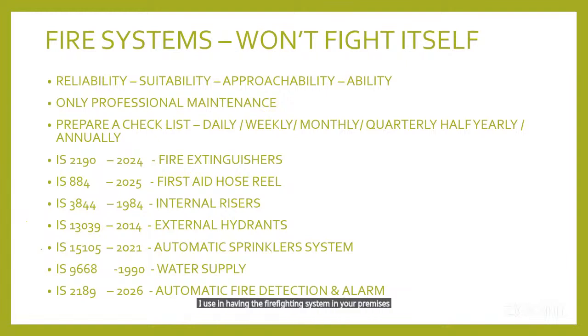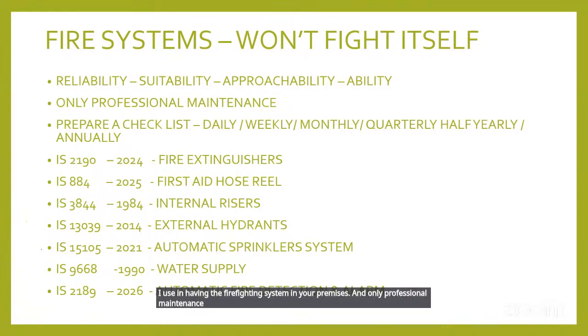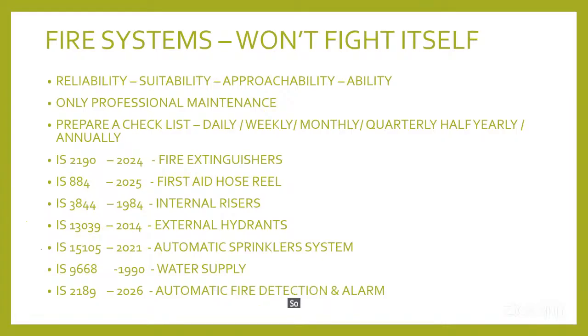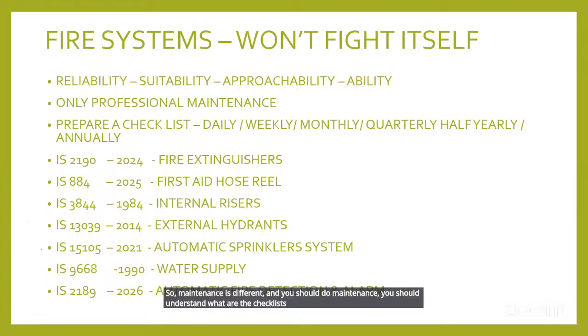And only professional maintenance counts. It is not a mere pasting of stickers on the extinguishers. I have seen many places while doing audits; only stickering is not maintenance. Maintenance is different, and you should do it. You should understand what the checklists are, what the requirements of a fire extinguisher are, what is specified in the concerned IS, what the test system is, and what the maintenance system mentioned in the IS is.